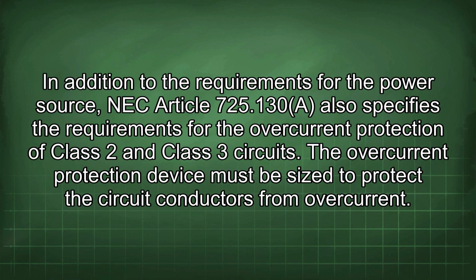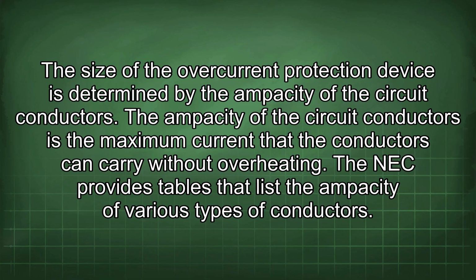In addition to the requirements for the power source, NEC Article 725.130 also specifies the requirements for the overcurrent protection of Class 2 and Class 3 circuits. The overcurrent protection device must be sized to protect the circuit conductors from overcurrent. The size of the overcurrent protection device is determined by the ampacity of the circuit conductors. The ampacity of the circuit conductors is the maximum current that the conductors can carry without overheating.